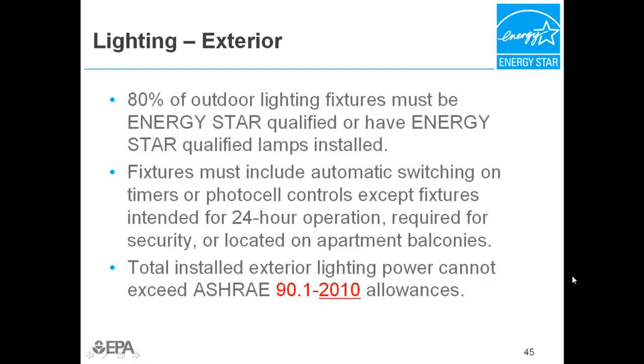Similar to indoor lighting requirements, 80% of the exterior light fixtures must be ENERGY STAR qualified or have ENERGY STAR qualified lamps installed. Exterior lighting fixtures must include automatic switching on timers or photocell controls. Fixtures intended for 24-hour operation, required for security, or located on apartment balconies do not have to meet this requirement. These are the same requirements as in the performance path. The one additional requirement is that the total installed exterior lighting power cannot exceed ASHRAE 90.1 2010 allowances.